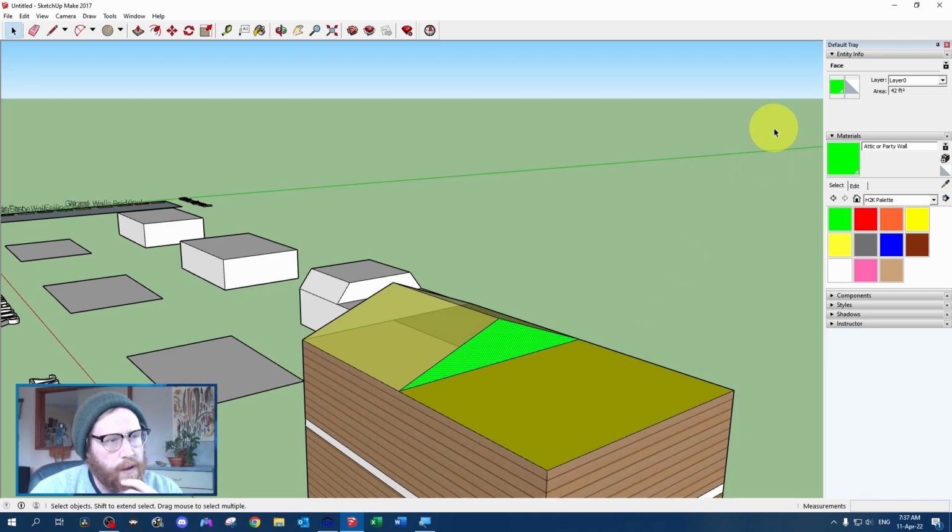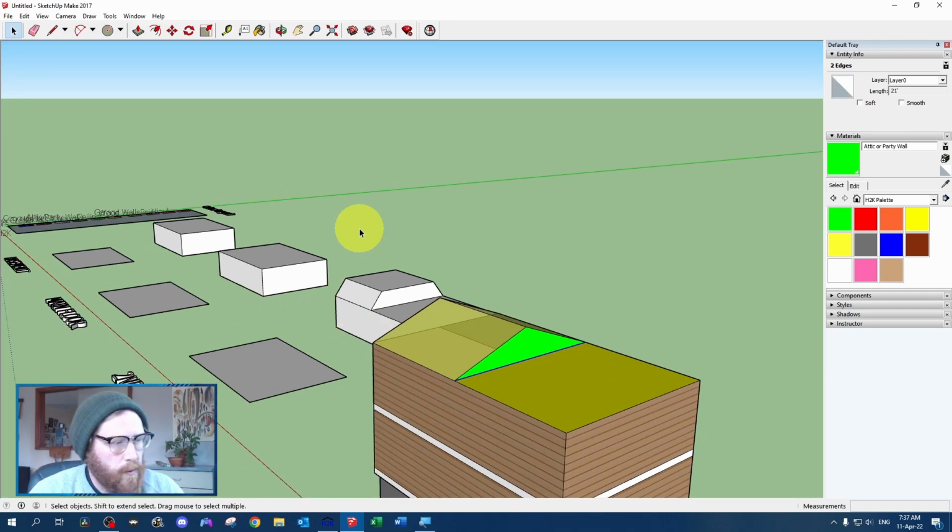And then to put that wall in, we would just do 42 feet squared divided by the full bottom perimeter. And you want to use the full perimeter because that's going to tell Hot2000 how many studs are in this wall for thermal bridging. So it would just be 42 divided by 21. So we'd just have a height of 2, our average height for the wall. And then we would use the 21 feet for our perimeter. But we'll cover that in Hot2000 here in a sec.